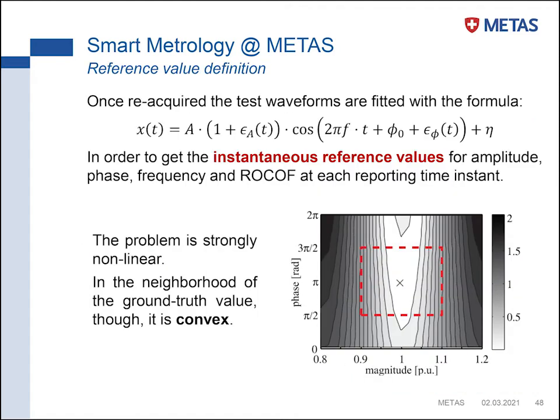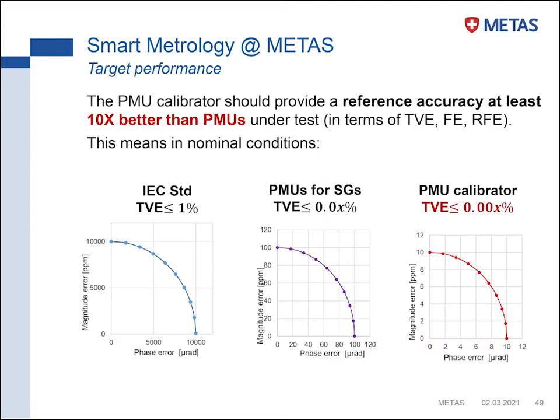Now, what are the main challenges? So the first thing is to be sure to be able to extract the reference values, and to do that, since the signal that has to be tested is not only purely sinusoidal, but also represents dynamic conditions, we have to do a nonlinear fit that is quite complicated on the reacquired waveforms, and that does not guarantee perfect convergence. But we made a study to guarantee that in the neighborhood of the reference values, our fit is converging to the optimal minimum of the fit cost function. So we are quite sure that the estimated reference values are correct, but the real problem is that we have a quite challenging target performance. So as any other calibrator, we have to guarantee an accuracy that is at least one order of magnitude better than the DUT.